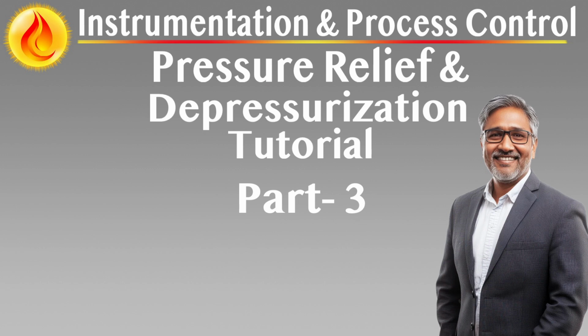Key design objectives include ensuring safe, continuous disposal of relieved gases under all operating scenarios, preventing exposure of personnel and equipment to toxic or flammable vapors, limiting environmental impact, noise, and thermal radiation, maintaining system integrity during simultaneous high-flow events from multiple sources. The upstream and downstream piping, headers, and flare tips must be designed holistically, considering all anticipated load cases and worst-case combinations of relief and depressuring flows.